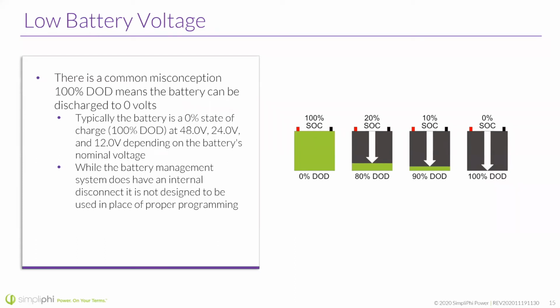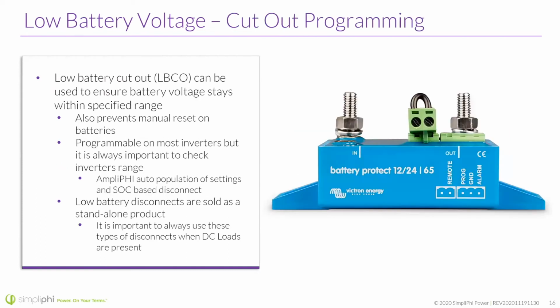And while the battery management system does have an internal disconnect, it is not designed to be used in place of proper programming, meaning low battery cutout. That's kind of the most important thing to keep an eye out for. That LBCO is the most crucial way to avoid over discharging the battery as far as the voltage is concerned.